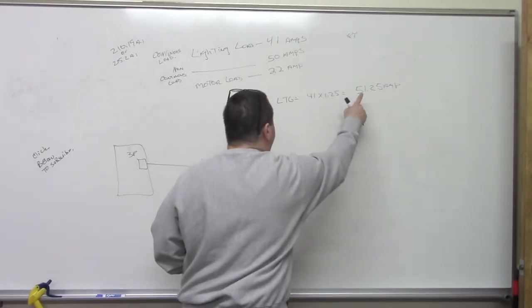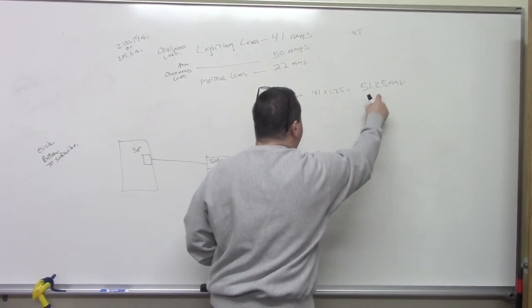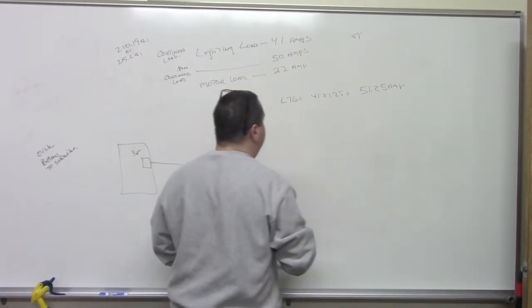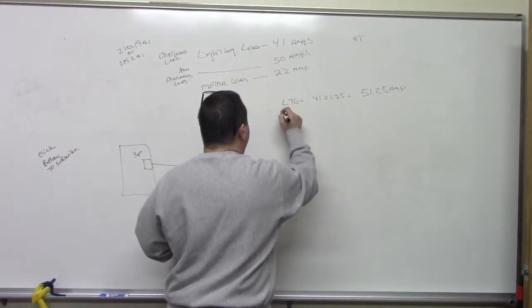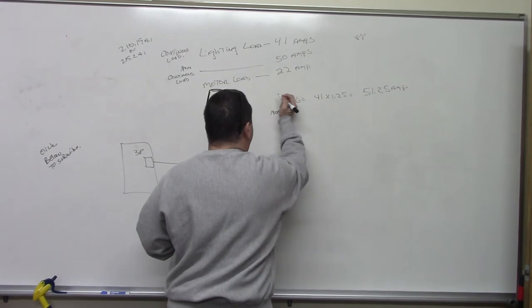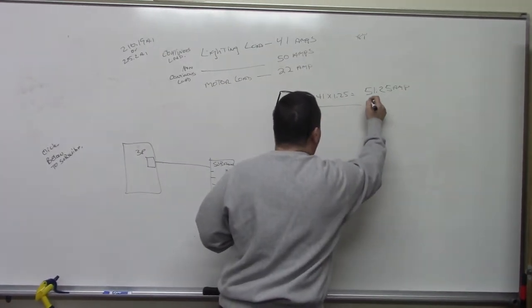So this is the real number now, 51.25. So you make sure your conductor is based on this, not the 41, okay? Then we have a continuous load, non-continuous, non-continuous at 50 amps.